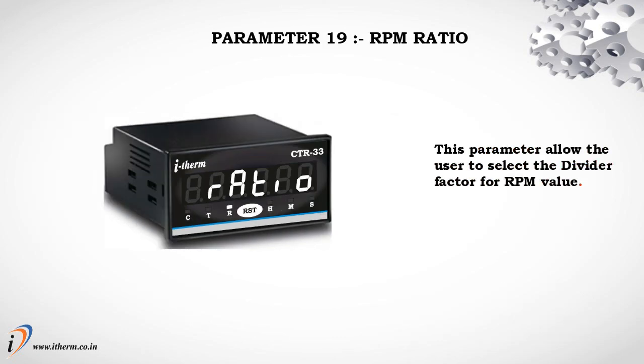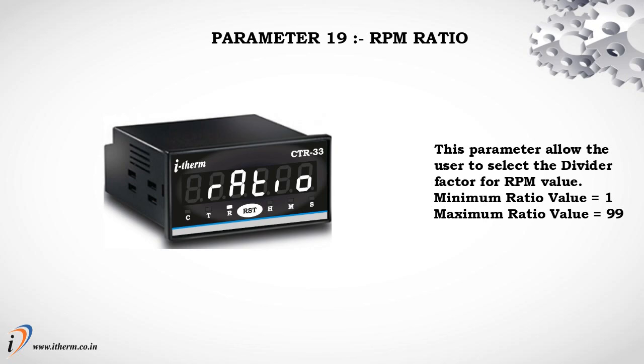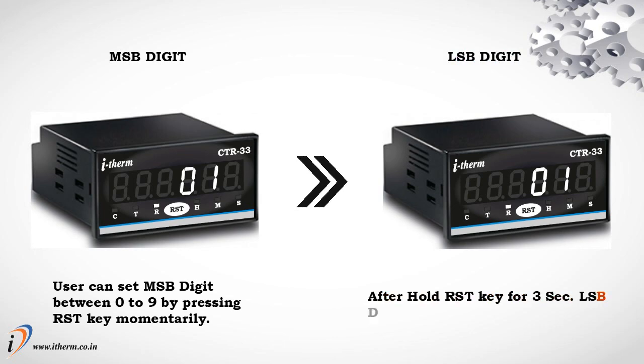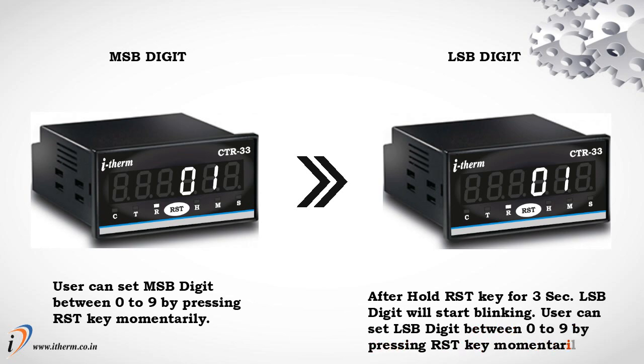Parameter 19: RPM ratio. This parameter allows the user to select the divider factor for the RPM value. The minimum ratio value is 1 and the maximum is 99. The user can set the MSB digit between 0 to 9 by pressing the reset key momentarily. After holding the reset key for 3 seconds, the LSB digit will start blinking and can be set between 0 to 9. This is the last parameter of the configuration list. Press and hold the reset key for 3 seconds to enter run mode.